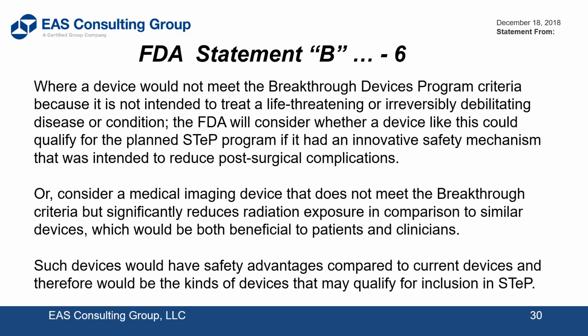So you notice if it doesn't meet breakthrough, it may meet STEP. Now, the STEP program is geared for safety issues that don't seriously compromise a person's health if there are problems. Breakthrough devices are dealing with technology that can affect patients' health and or life itself. So breakthrough is a higher level. STEP is a little lower level, where you're showing improvements of safety or reduction in number of interventions and things like that for your device to qualify for one of those two programs.